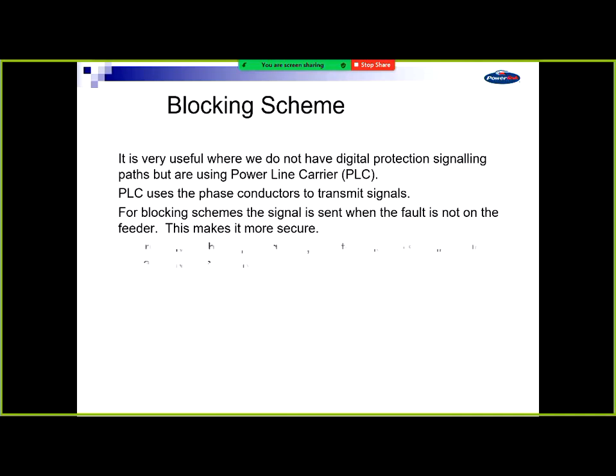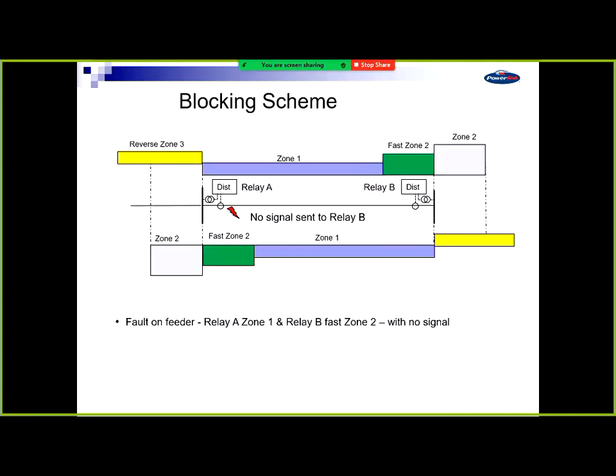Yeah, that's what I've said. We go fast if you don't get the signal. It was good with power line carrier. So for that fault which was in a zone 2 before, if we've got a blocking scheme, you see that now there's these reverse zone 3s in yellow from each end, and they extend beyond their remote zone 2s. So we're covering those there. So for that fault, relay A goes instantaneously, relay B sees it in its fast zone 2 time, so it waits about 50 milliseconds to receive that signal from the remote end. If it doesn't get it, it trips. So we'll leave that at that step.